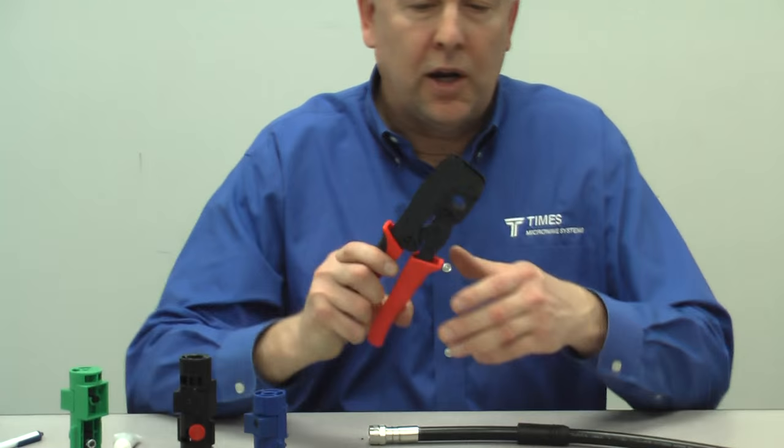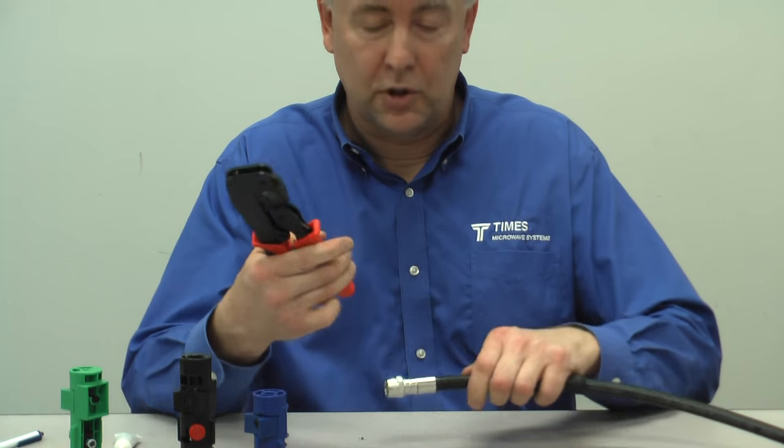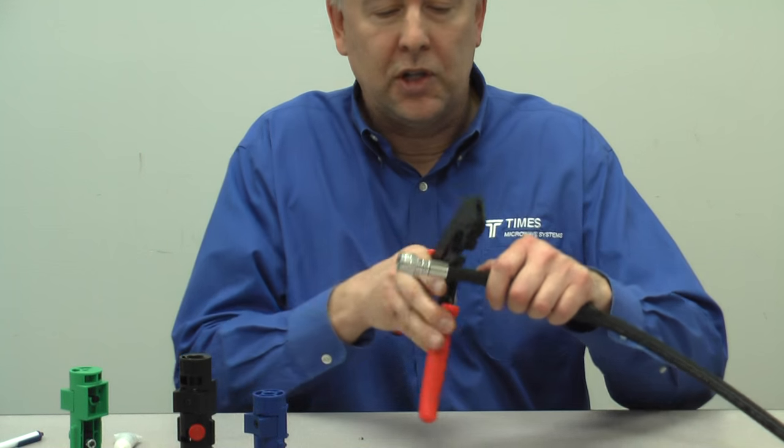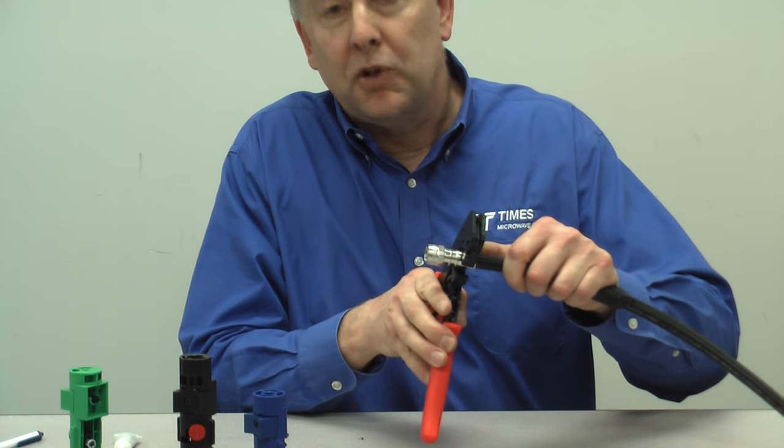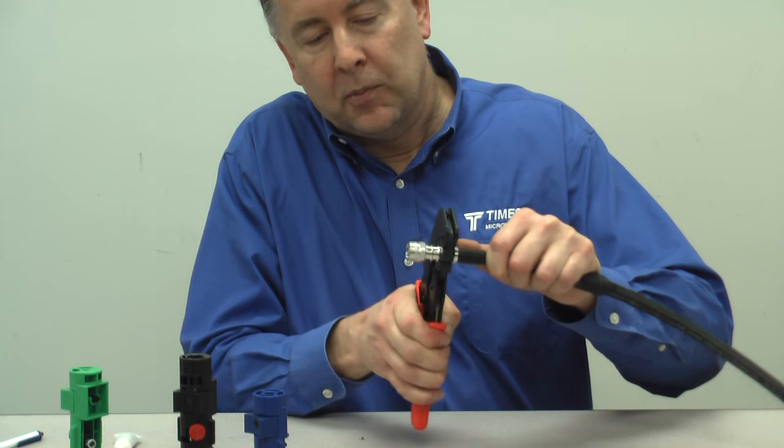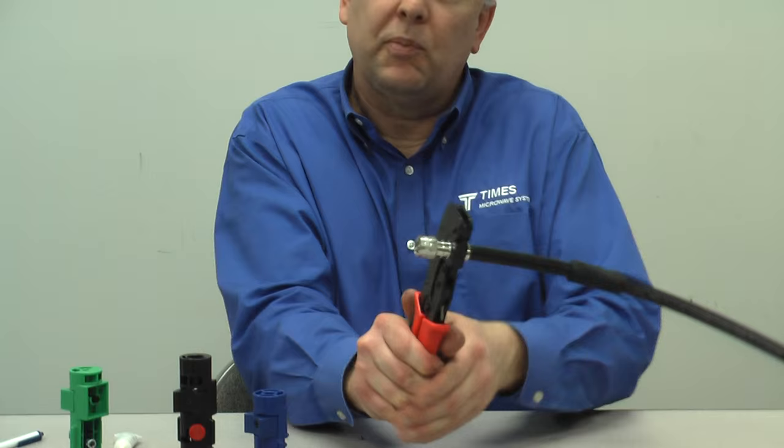You have a couple choices here now. We have our new CT-DEF 600 crimp tool. You can use the CTU universal crimp tool with the interchangeable dies, but for our purposes, the nice economical CT-600 tool. You want to crimp it just once. You want to crimp it right at the very back of the connector. Just crimp that all the way down.